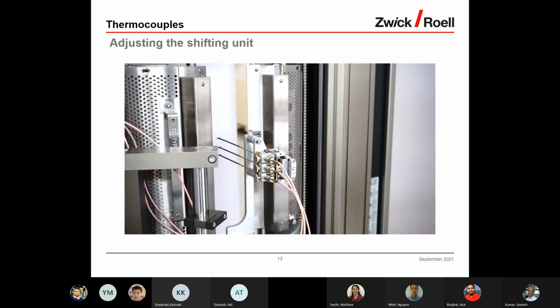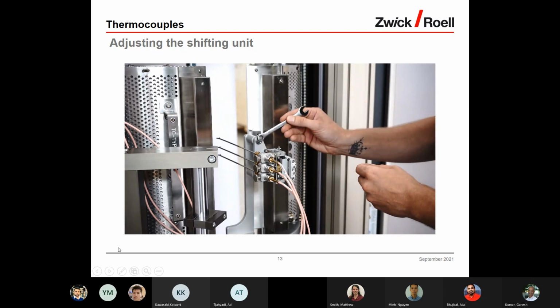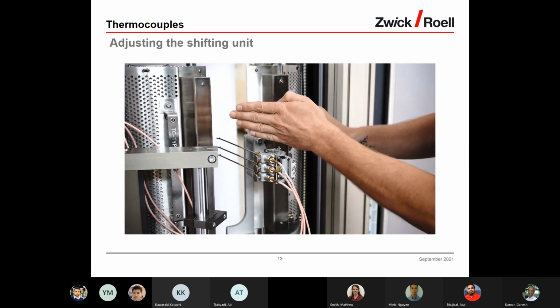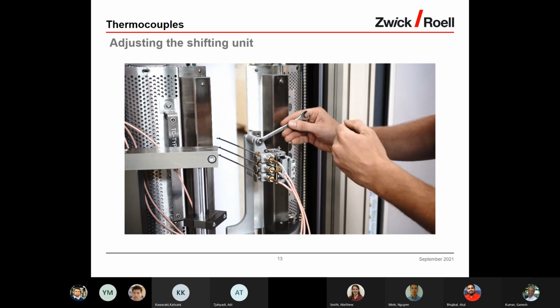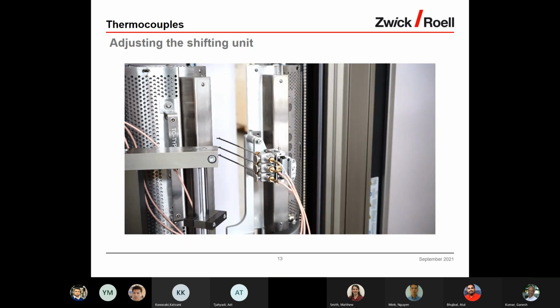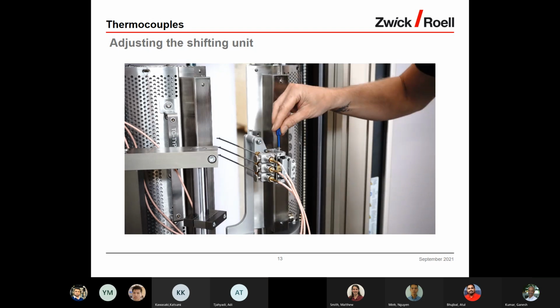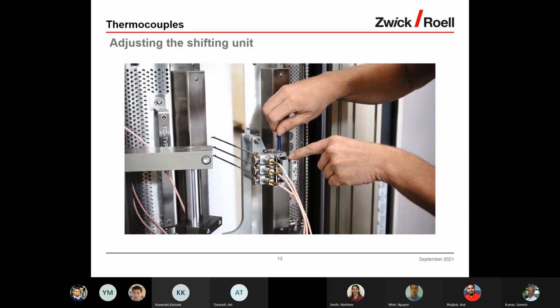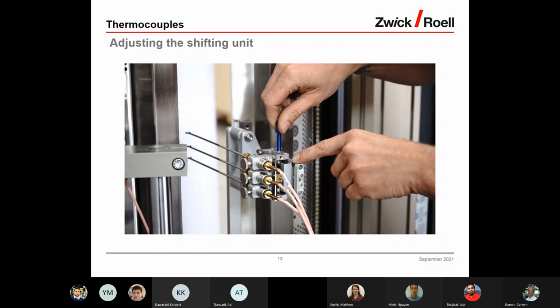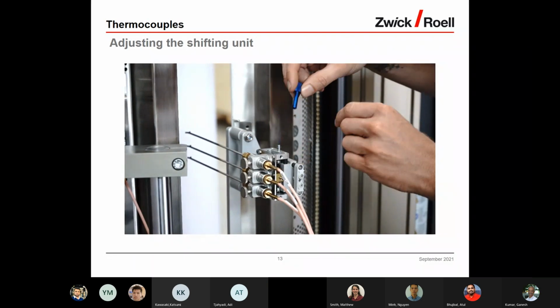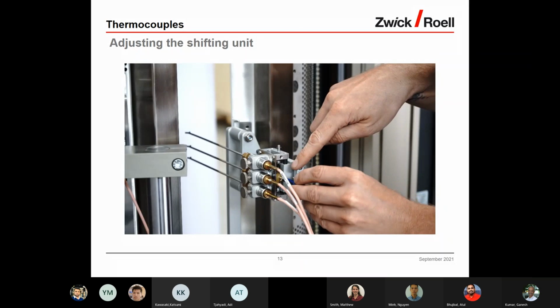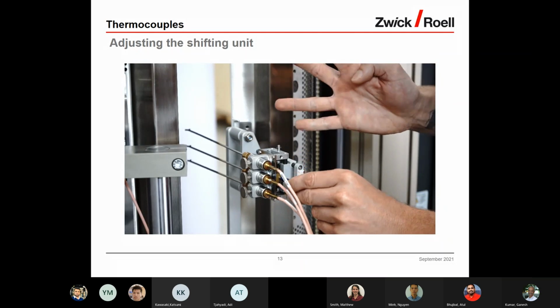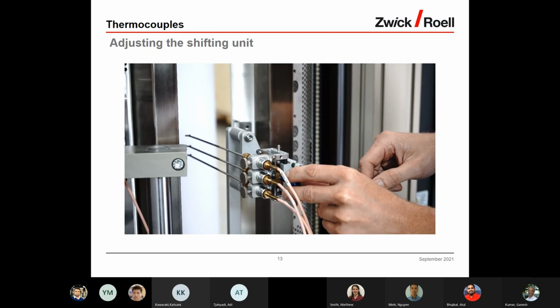Adjusting the shifting unit. This is also a small movie. By opening the two nuts, the TC unit can be adjusted in height and laterally into the center of the furnace. With the supplied tool from Mitec, you can adjust the height of the unit. At this position, it is possible to set the spreading of the thermocouples.